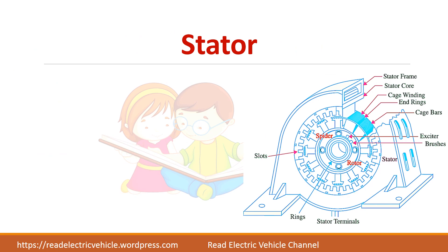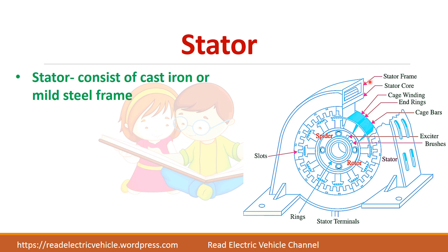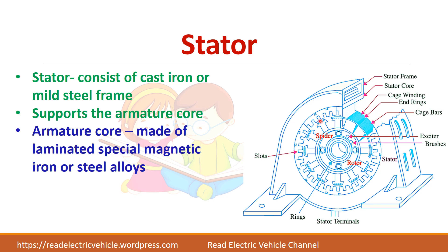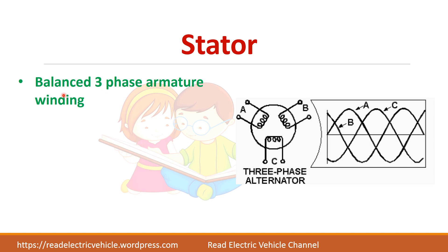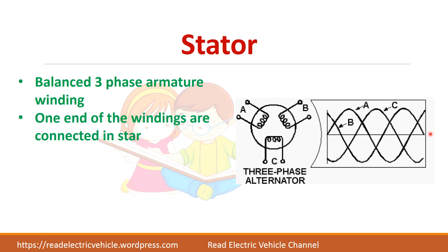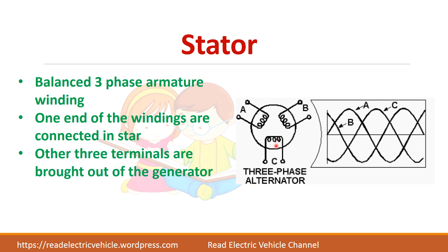First let us see about the stator. This is the constructional view of the three-phase alternator. The stator frame is the outermost part, which protects the stator core or armature core, and there are slots to keep the stator windings. This armature core consists of a three-phase armature winding — three armature windings displaced by 120 degrees. One end of the windings are connected in star and the other ends are brought out for taking the output.